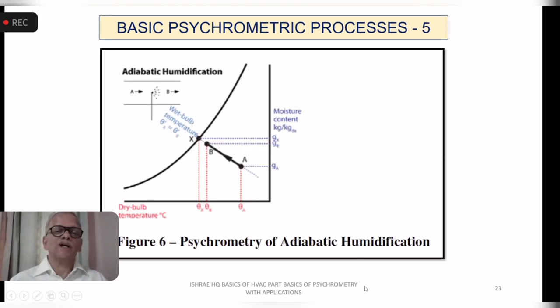The next process is adiabatic humidification. There is no change in the enthalpy, but you are changing the point entering at A with this dry bulb and this moisture content and moving along the wet bulb line. You have a spray adding moisture to the airstream. That is the apparatus in this case. The moisture gets added and cools the air moving over it. So there is a reduction in the dry bulb temperature, but an increase in the moisture content. This is your desert cooler application, or the air washer application, which is very commonly used in the textile industry.